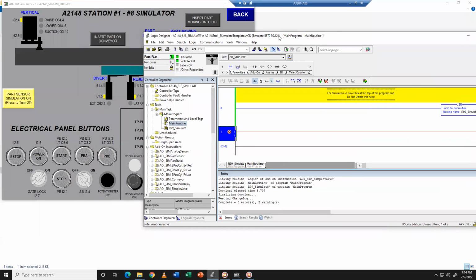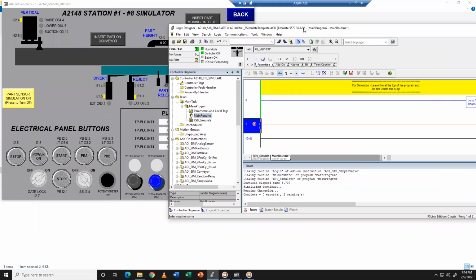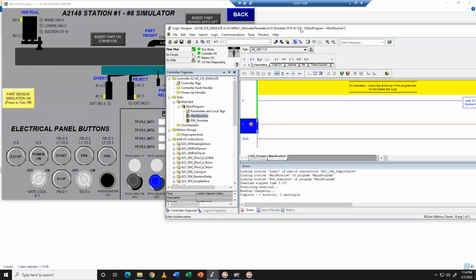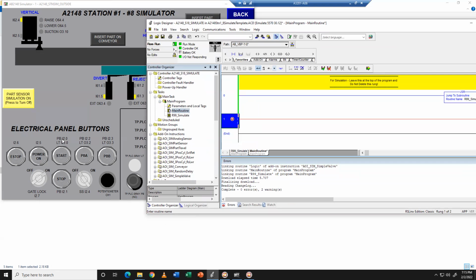So we're going to work in tandem with our graphical interface. We want to create logic where if start push button, this one, is pressed, then light A, which is the light associated with push button A, turns on. Now, there are IO lists and tables, which you got last week, that you can look these things up, or by looking at these tags, I know that input 20 is the push button input for the start button, and the light output is 032.